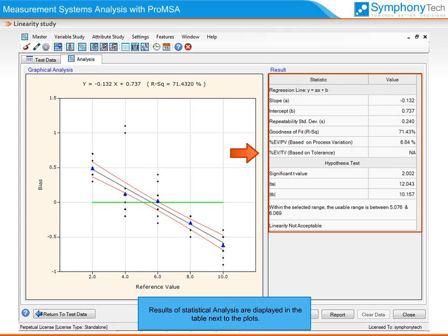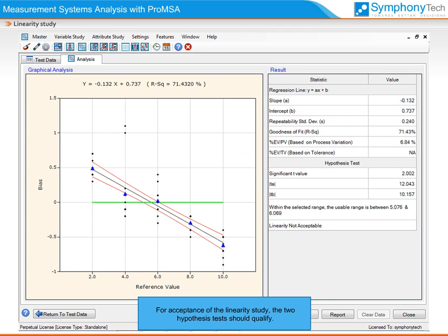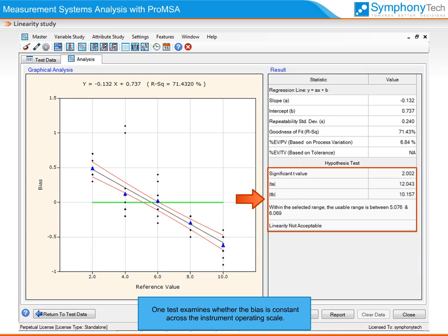Results of statistical analysis are displayed in the table next to the plots. For acceptance of linearity studies, two hypothesis tests should qualify. One test examines whether the bias is constant across the instrument operating scale, and the other test examines whether the bias is not significantly different from zero.